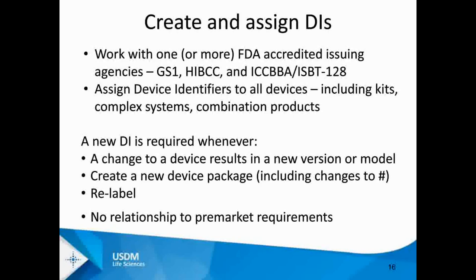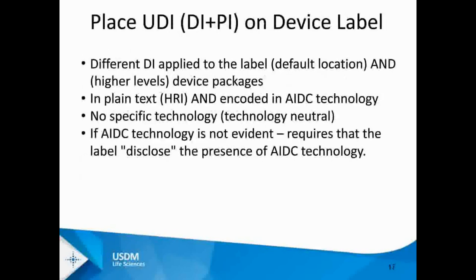Once device identifiers are created, they go on the label along with production identifiers — that's where the two components come together into the UDI. The UDI must be in plain text (human readable) and encoded in some form of AIDC technology — linear barcodes, two-dimensional barcodes, or RFID. FDA did not limit or constrain the technology; it just requires an appropriate AIDC technology per your issuing agency.